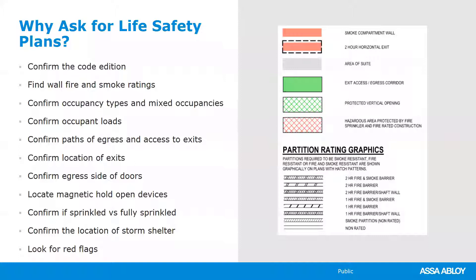Confirm the occupancy types and look for mixed occupancies. You want to confirm occupant loads — they should be listed depending on the complexity of the project. You need to confirm paths of egress and access to exits, as well as the location of exits and confirm which side is the egress side of the door. If the owner wants card readers on some doors and you're locking a door on the path of egress, you may need to consider a special locking arrangement.